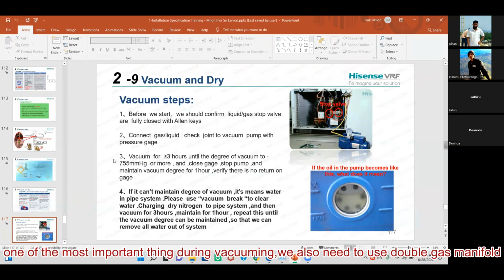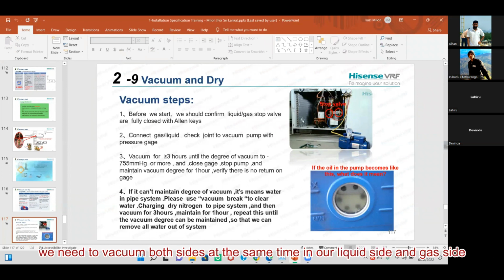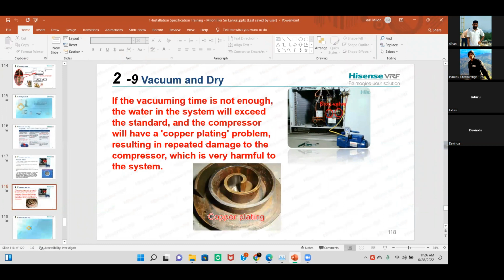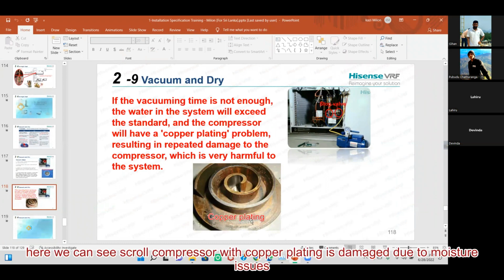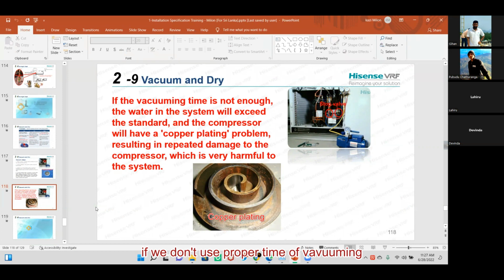One of the most important things during vacuuming is that we also need to use a double gauge manifold. We need to vacuum both the liquid side and gas side at the same time. Here we can see the scroll compressor copper plating is damaged due to moisture issues. If our vacuuming is not enough, then we will face these types of problems.